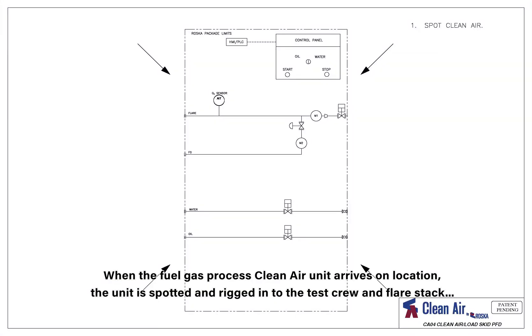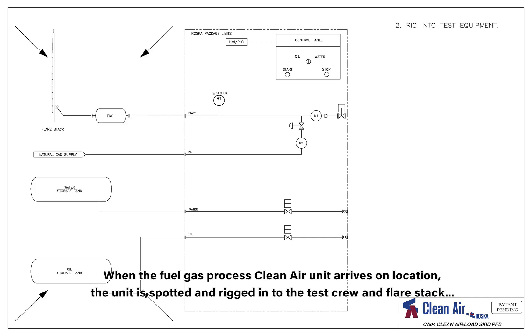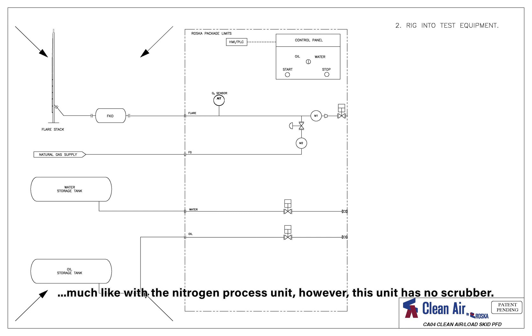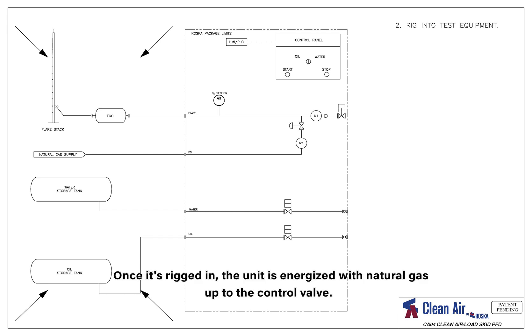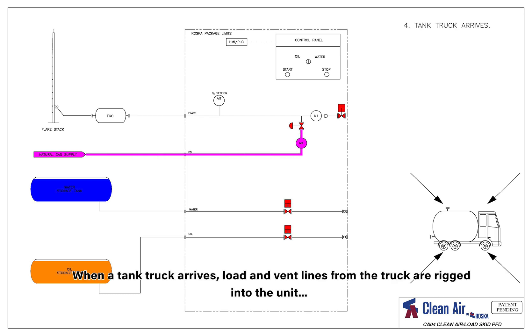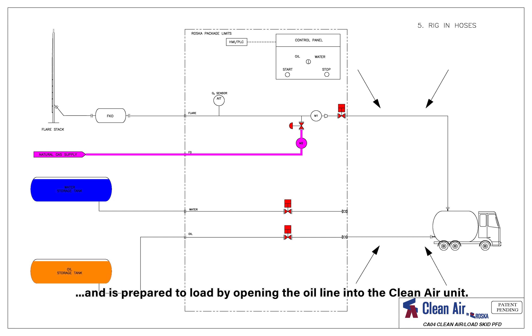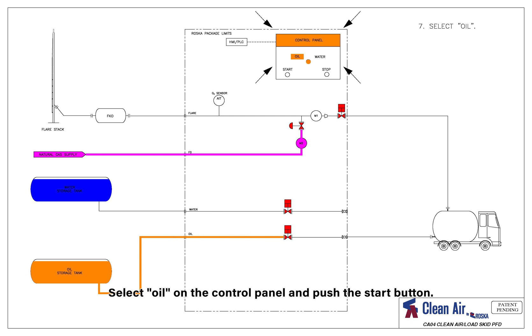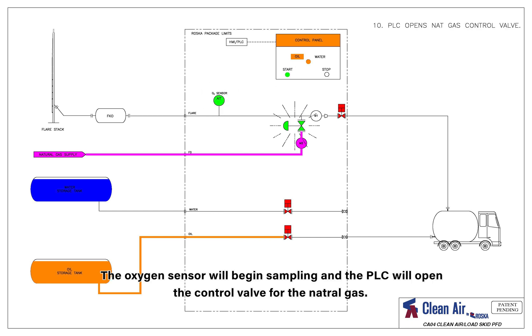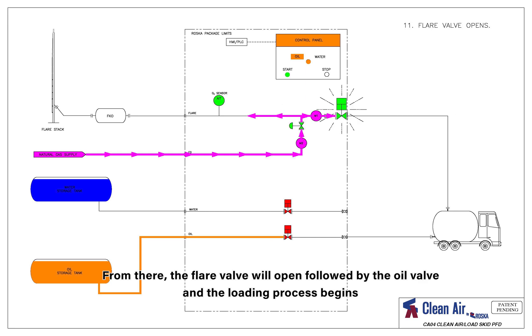When the fuel gas process Clean Air unit arrives on location, the unit is spotted and rigged into the test crew and flare stack. Much like with the nitrogen process unit, however, this unit has no scrubber. Once it's rigged in, the unit is energized with natural gas up to the control valve. When a tank truck arrives, load and vent lines from the truck are rigged into the unit and it is prepared to load by opening the oil line into the Clean Air unit. Select oil on the control panel and push the start button. The oxygen sensor will begin sampling and the PLC will open the control valve for the natural gas. From there, the flare valve will open followed by the oil valve, and the loading process begins.